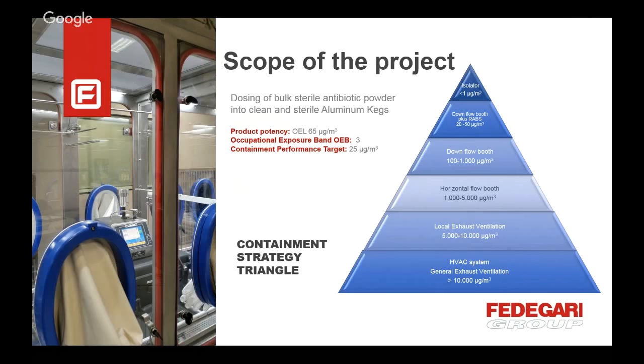Then we have a simple downflow booth, providing protection between 100 and 1,000 micrograms per meter cube. In the case of a less dangerous product, you can even have just a horizontal flow booth with an airstream taking the powder away from the operator, and we can move to a less sophisticated solution with local exhaust ventilation. And then at the end, we can make some containment even with the centralized HVAC system by establishing a good pressure gradient between the rooms. So the containment room has to be at negative pressure against the other rooms in order to contain all the product, the powder, the dustiness generated within the room.